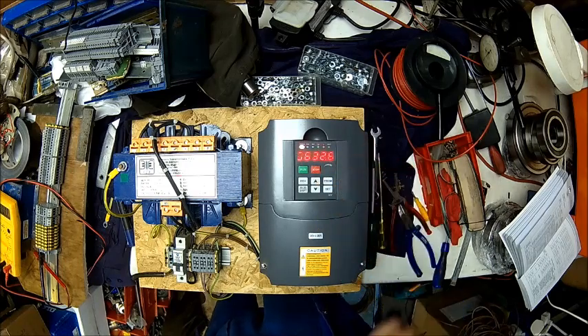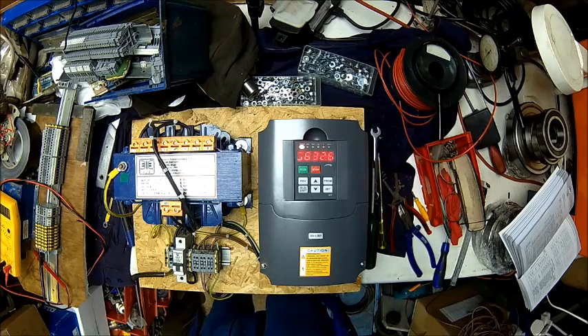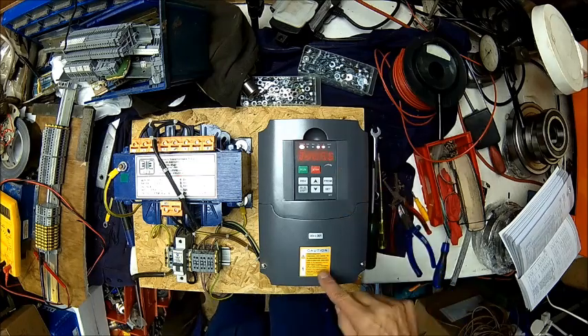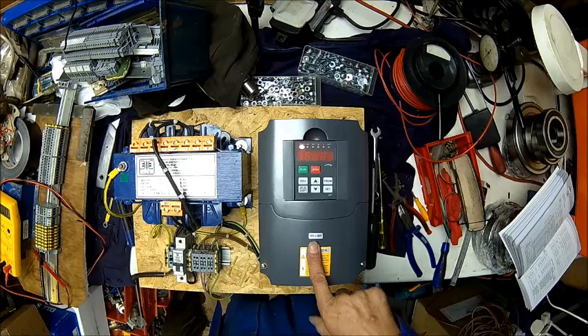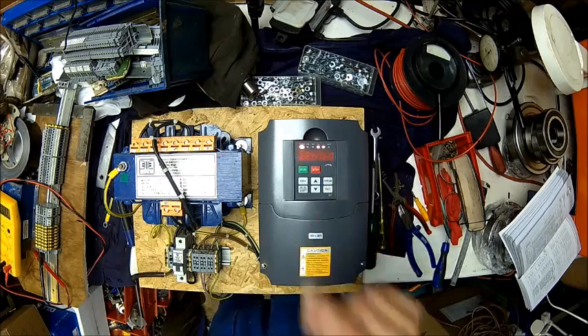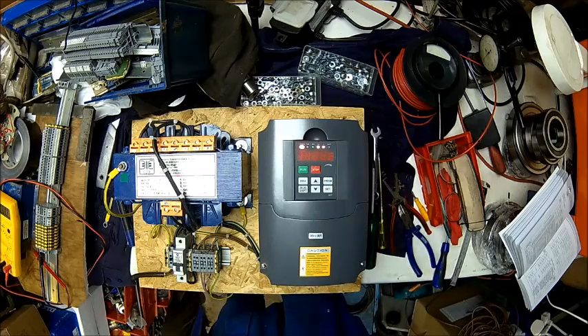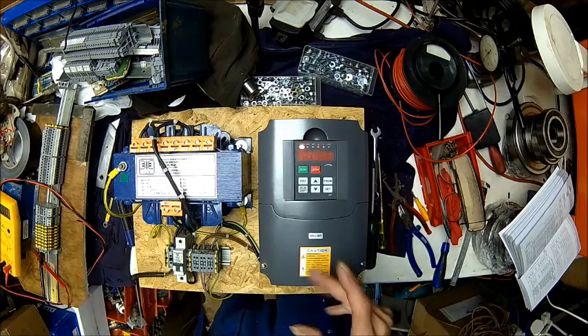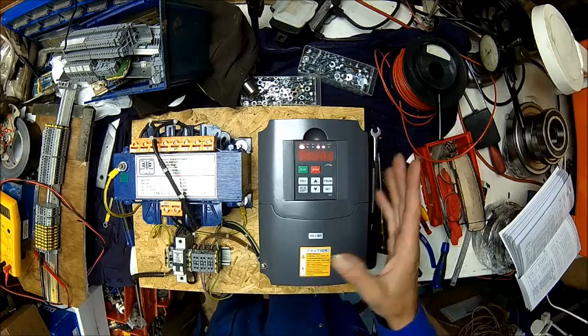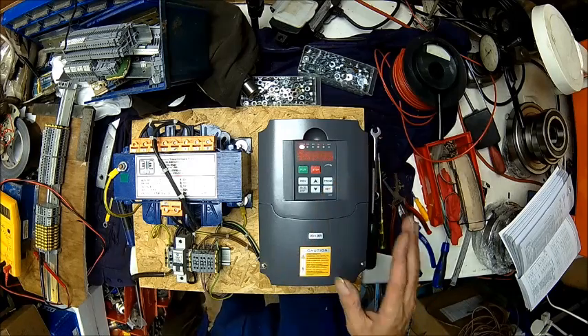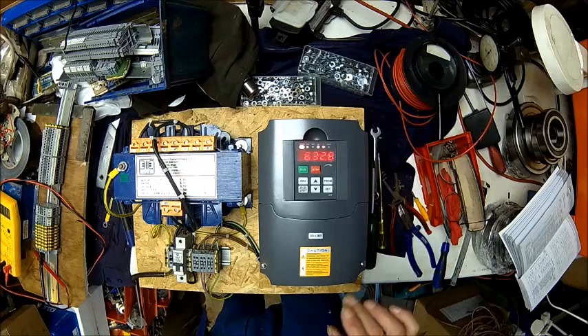See, if you stop, it goes up to that voltage here, and so that's the idle voltage of the rectified mains, 415 volts or 440 volts in, times square root of 2, because it's only single phase. If three-phase rectifier, it's about 1.6, so it's more like 680, 690, which is probably a bit too much for that one.